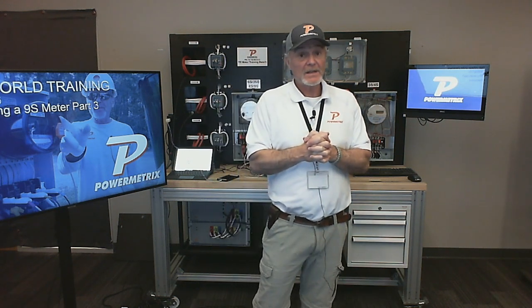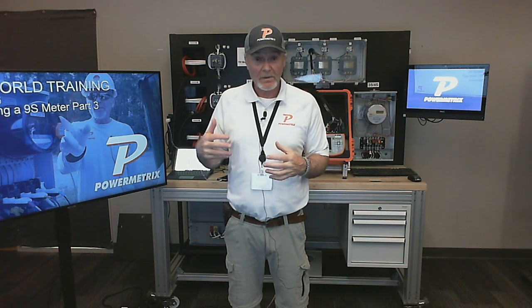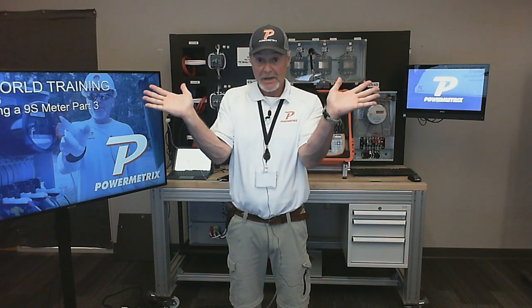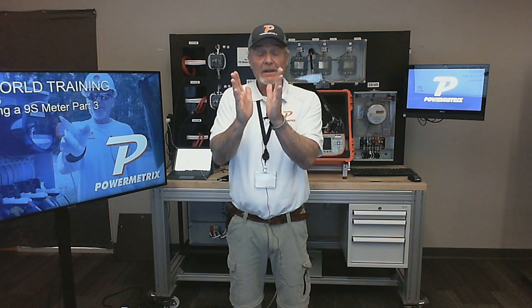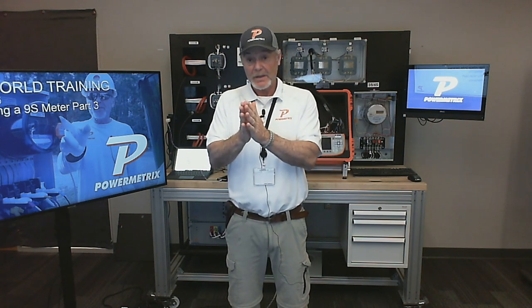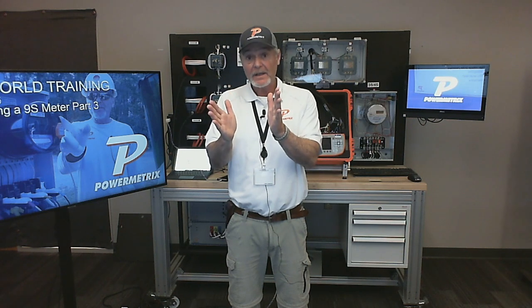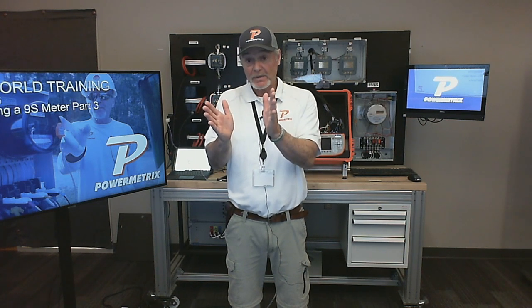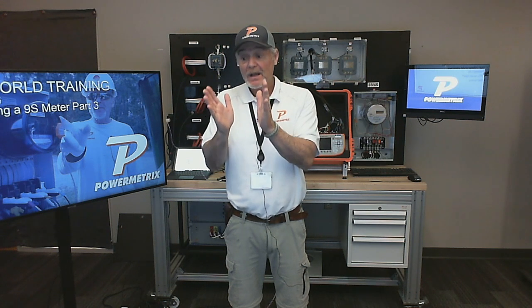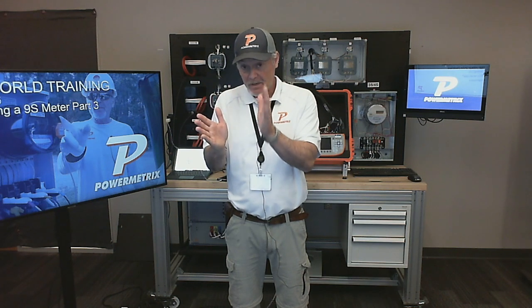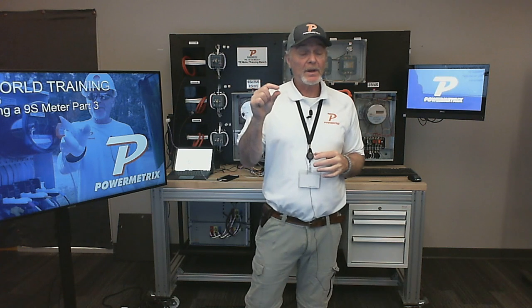So far so good. We didn't like the size of the angles between the vectors on each phase. That tells you about polarity reversal if it's really bad, like 180 degrees. But even if it's just a wider angle, it tells you that you're losing more money because of bad power factor. The bigger the angle between the current and voltage vectors on the same phase, the worse the power factor, and by worse we mean a smaller number.